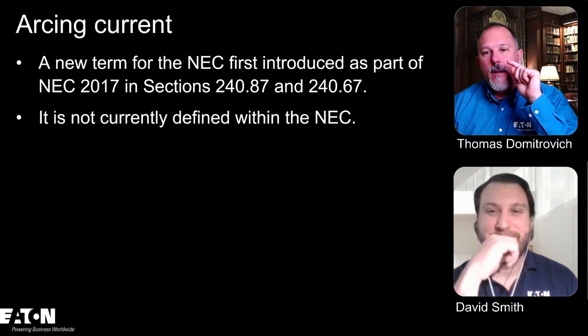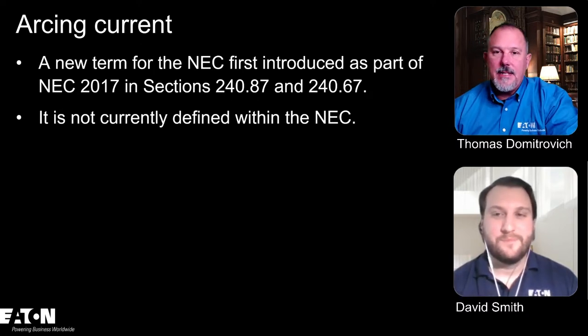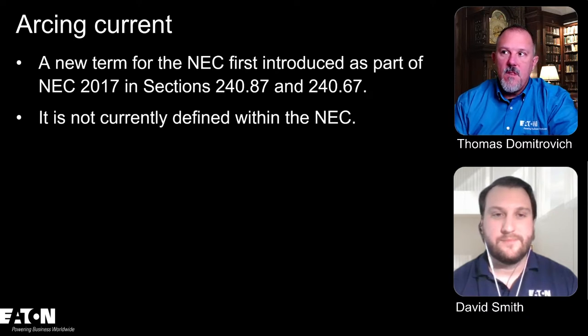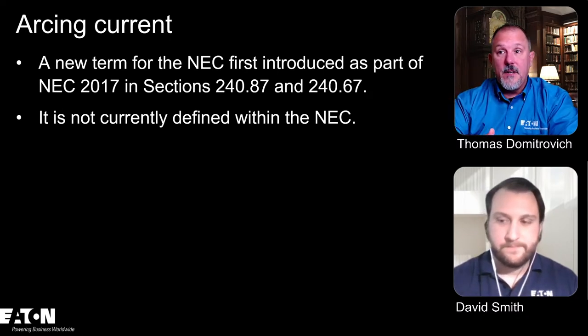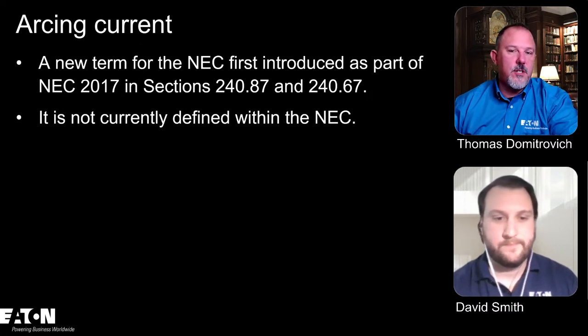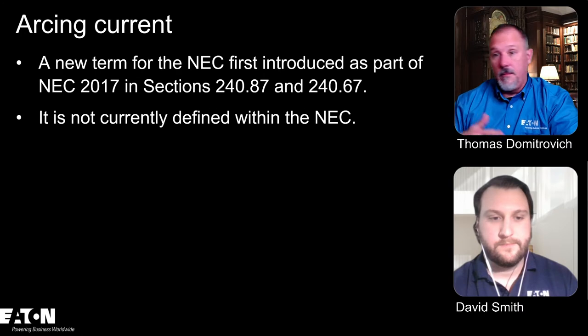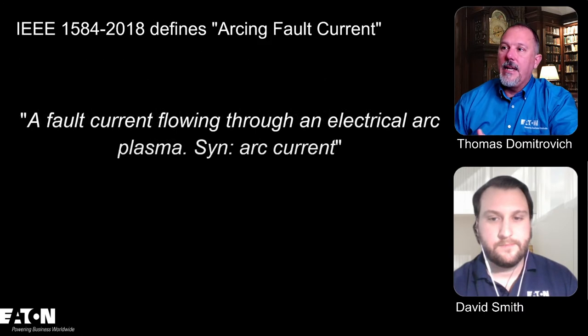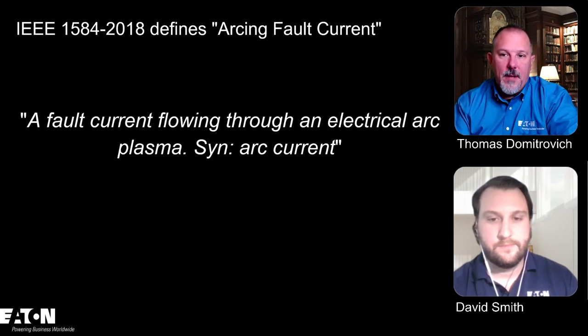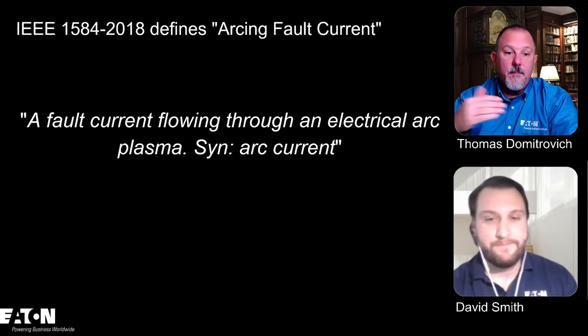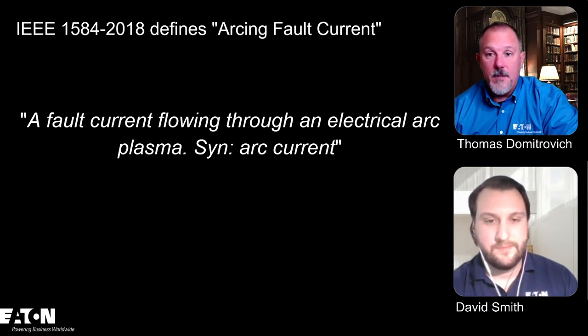So arcing current is a new term. It's not defined within the NEC. It is defined in 1584, but the way it's defined is not really going to help you in applying 240.87, because it just says the arcing current is through a plasma, blah, blah, blah. It doesn't tell you if it's the minimum or maximum, right? But in any case, arcing current's a new term. There's your 1584 definition: a fault current flowing through an electrical arc plasma. Okay, it doesn't tell you if it's the minimum or maximum, or if there is a minimum and maximum. It's just the electrical arc flowing through a plasma.